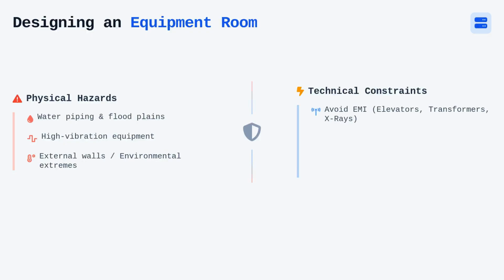Avoiding electromagnetic interference is a non-negotiable design constraint, meaning we must distance our core switching and PBX systems from elevator motors, high-voltage transformers, or medical diagnostic tools like X-ray machines. These sources introduce noise that degrades signal integrity across sensitive backbone cross-connects.